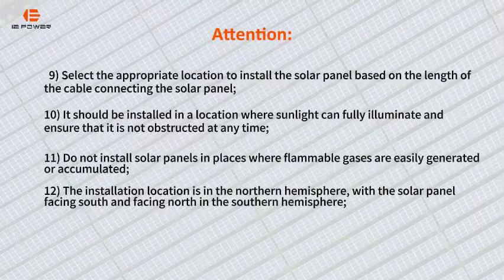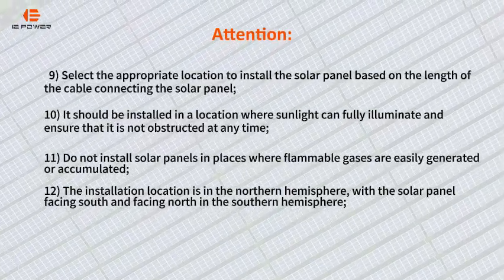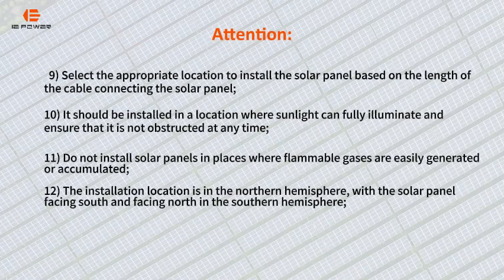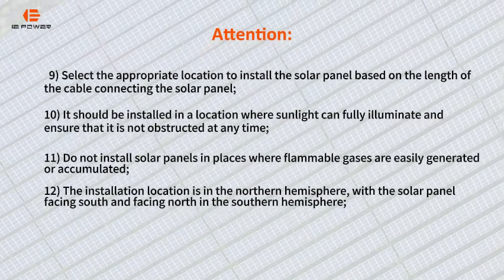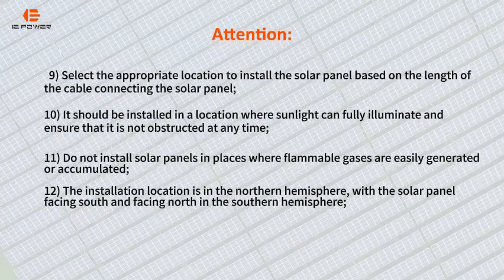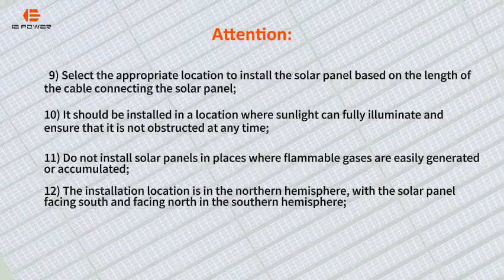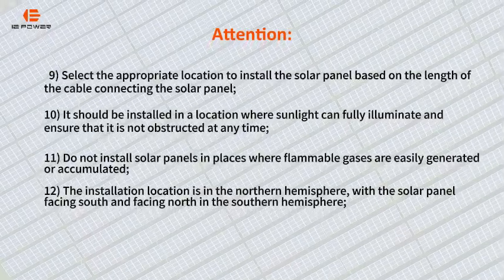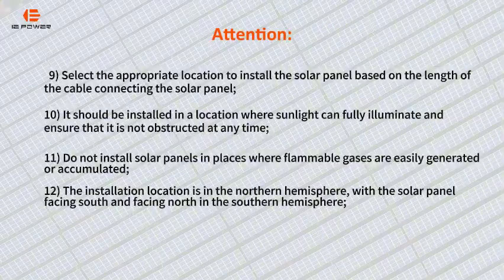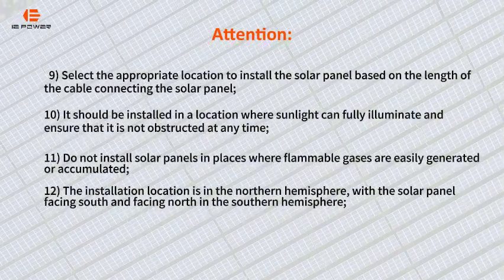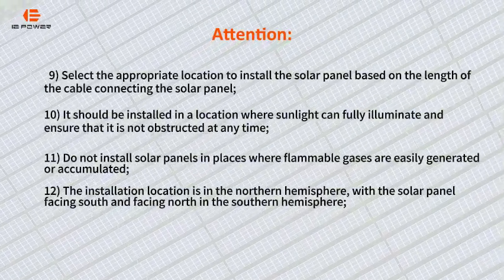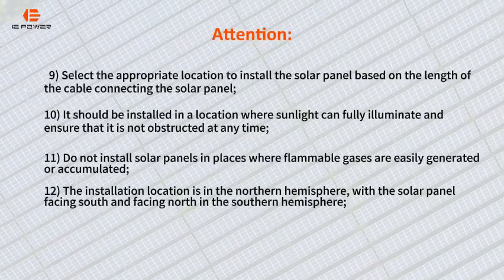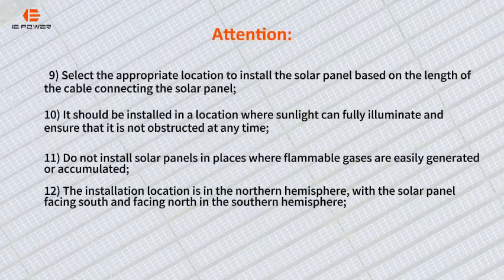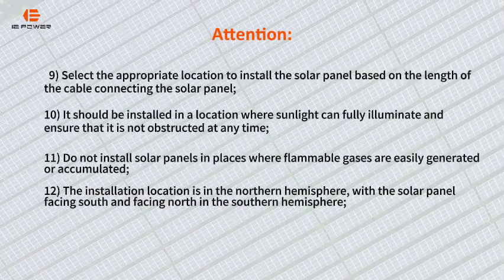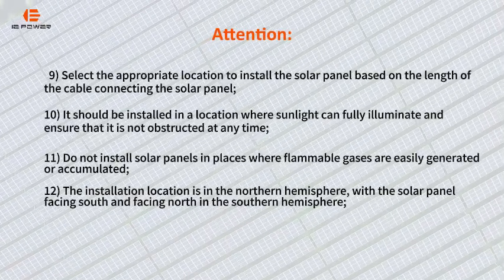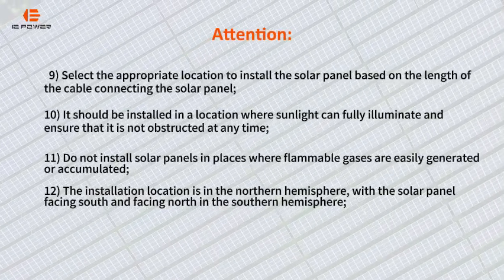9. Select the appropriate location to install the solar panel based on the length of the cable connecting the solar panel. 10. It should be installed in a location where sunlight can fully illuminate and ensure that it is not obstructed at any time. 11. Do not install solar panels in places where flammable gases are easily generated or accumulated. 12. The installation location is in the northern hemisphere, with the solar panel facing south, and facing north in the southern hemisphere.